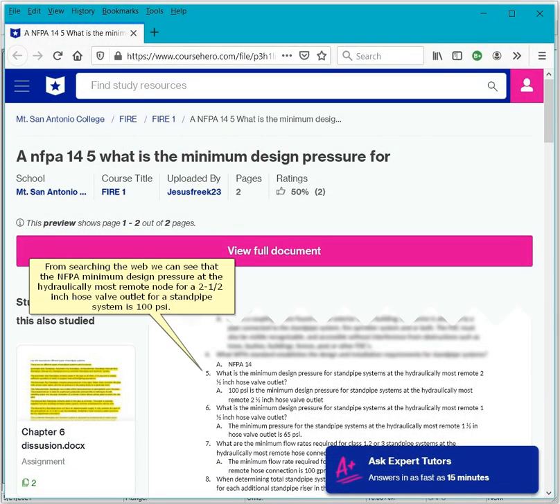From searching the web, we can see that the NFPA minimum design pressure at the hydraulically most remote node for a 2.5 inch hose valve outlet for a standpipe system is 100 PSI.